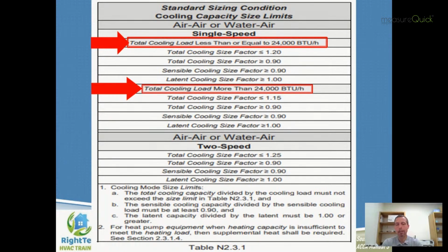But I always go back and tell people, at the end of the day, you want to size as close to the load as possible. We want to be as close to or slightly over that 100% mark. We don't want to have any unnecessary excess total capacity on this machine if we want to have a good, efficient system, particularly one that's going to run and dehumidify well when we're at part load conditions. And most of you guys know that we spend most of our load hours every year, something like 98% of them, at part load comfort conditions, when it's less than design temperature outside in the summer or greater than design temperature outside in the winter months.